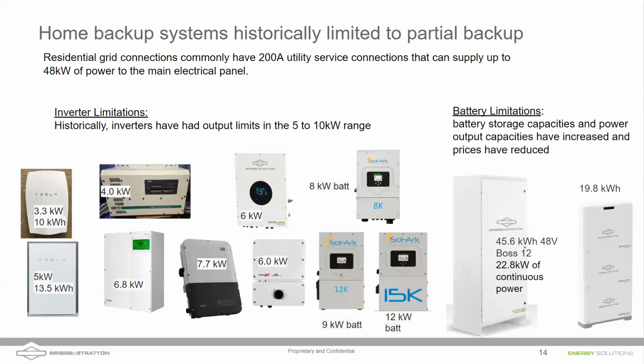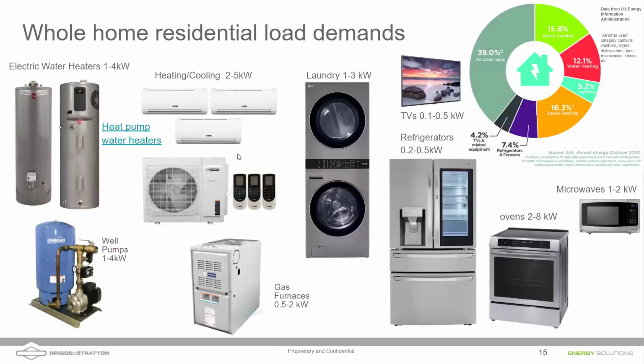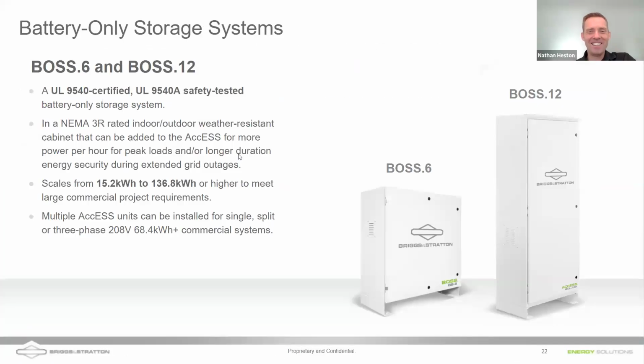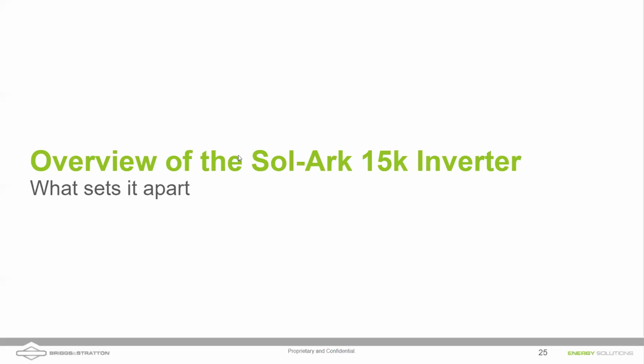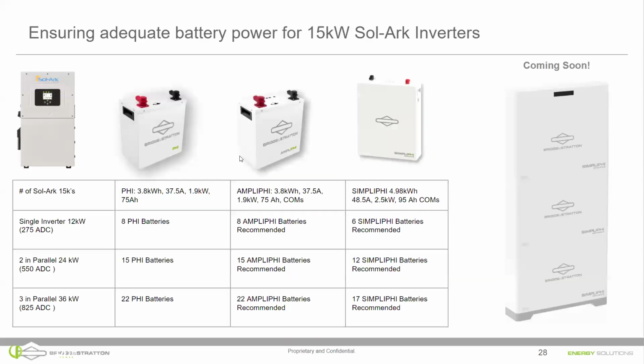Earlier, you showed a picture of the Sol-Ark with that two. I was trying to find... yeah, go ahead, Daniel. The question is, if we have two separate battery banks, do we need two different comm ports, or is the one comm port able to communicate to both battery banks? You should not have two separate battery banks. Well, I think what we're showing is that the Sol-Ark 15K has two battery breakers. Yeah, but essentially you have one battery bank that is combined at that battery breaker. So they're paralleled up there.